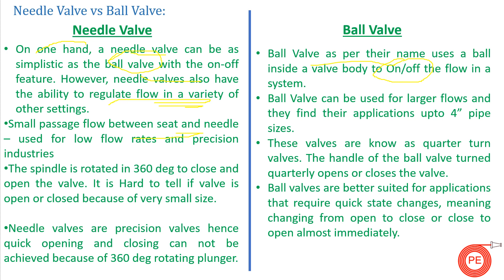Because of the small passage between the seat and the needle, needle valves are used for low flow rates and are generally available in very small sizes. Ball valves, on the other hand, can be used up to four-inch sizes. Above four inches, we typically go for gate valves or globe valves when flow control is needed. Ball valves are generally used up to DN100 or four-inch pipe size.